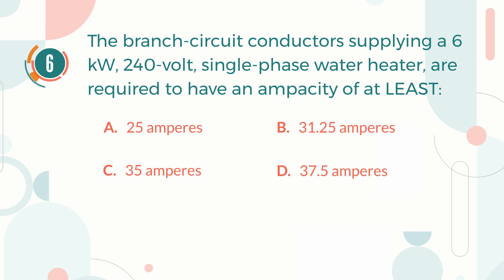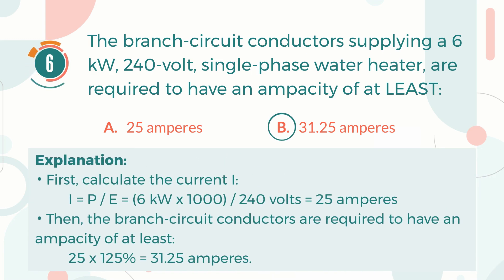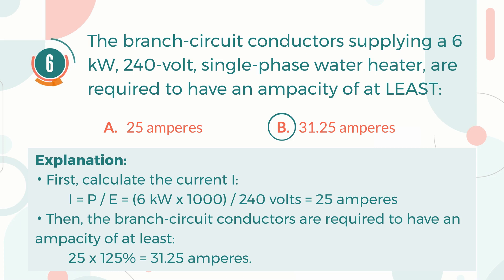The correct answer is B. 31.25 amperes. Explanation: First, calculate the current — power divided by voltage equals 25 amperes. Then, the branch circuit conductors are required to have an ampacity of at least 1.25 times 25 amperes, which is 31.25 amperes.